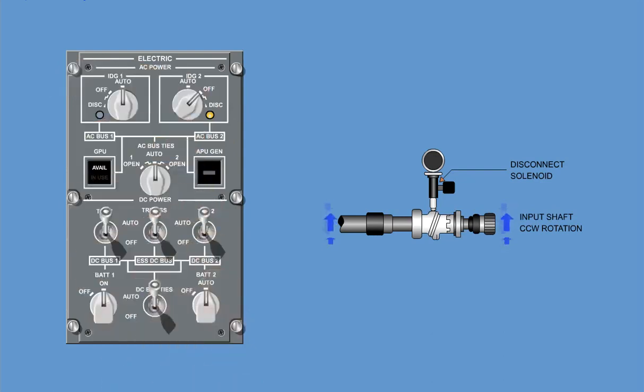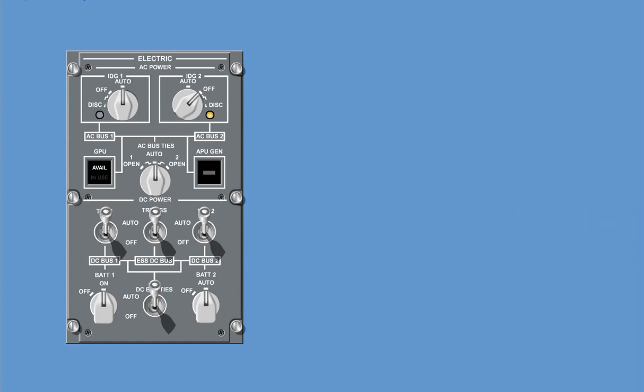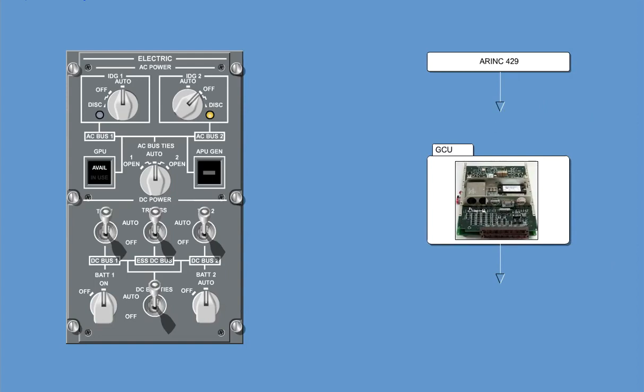Selecting the switch to the disc position causes the solenoid pin to retract. This action releases a plunger which engages the cam on the transmission shaft. As the shaft rotates, the plunger rides along the cam, moving the shaft axially away from the input shaft. The IDG input shaft part remains engaged with the drive spline of the gearbox. A signal is also passed over ARINC 429 to the respective GCU to trip the generator control relay and the generator line contactor.